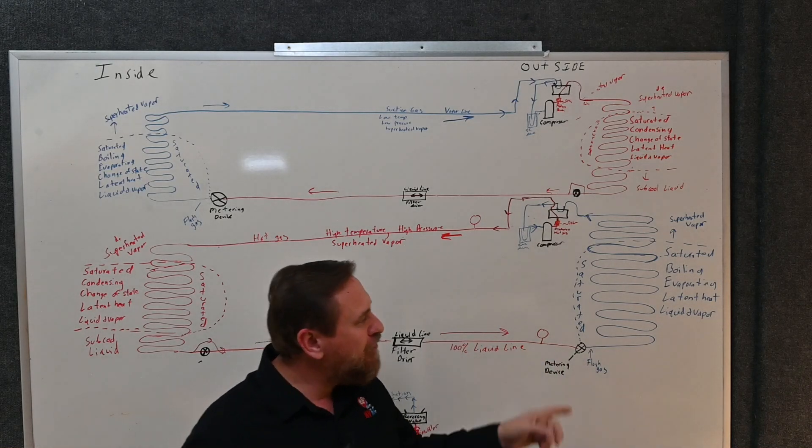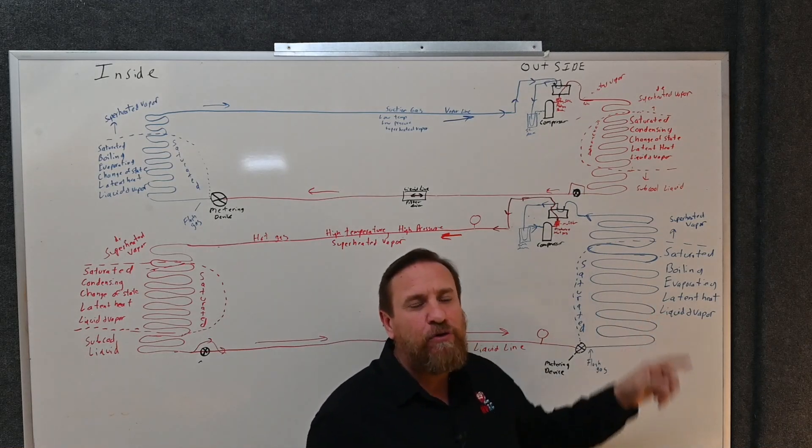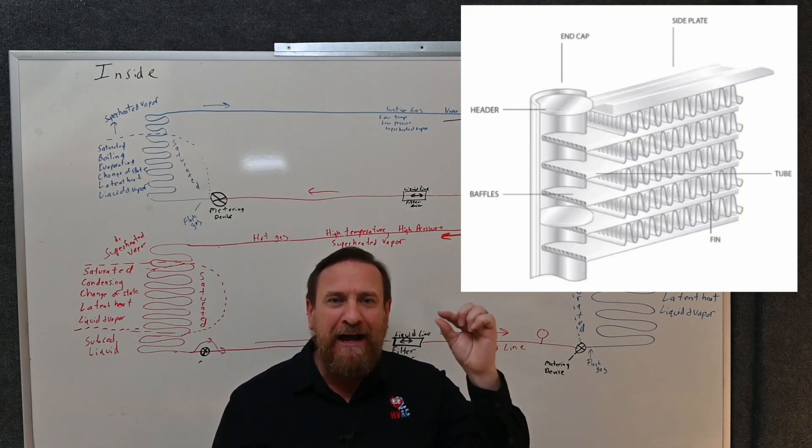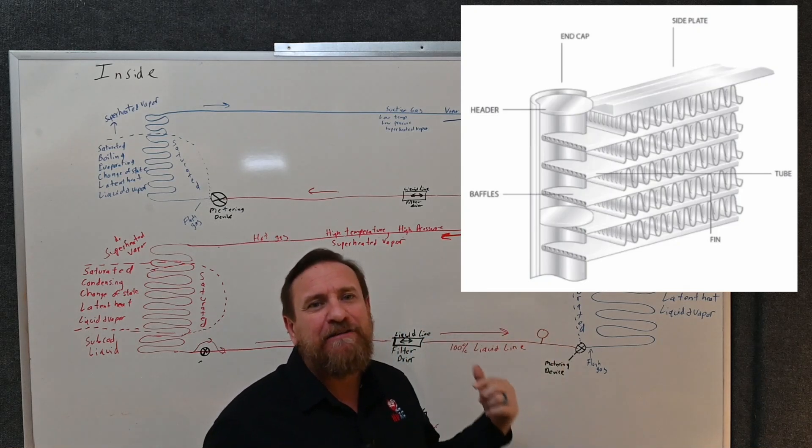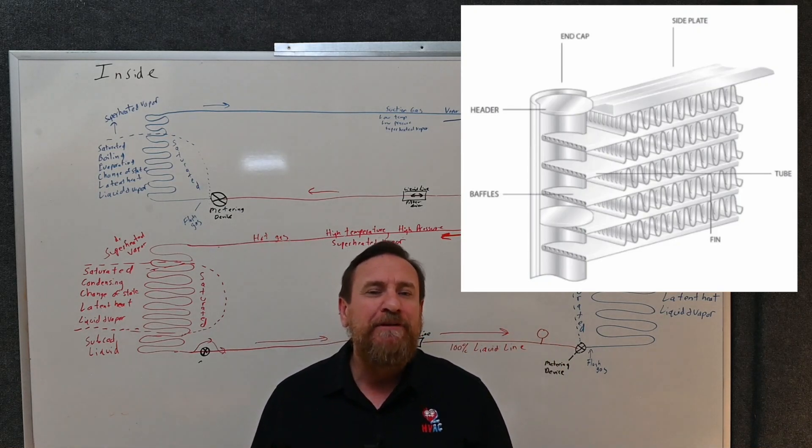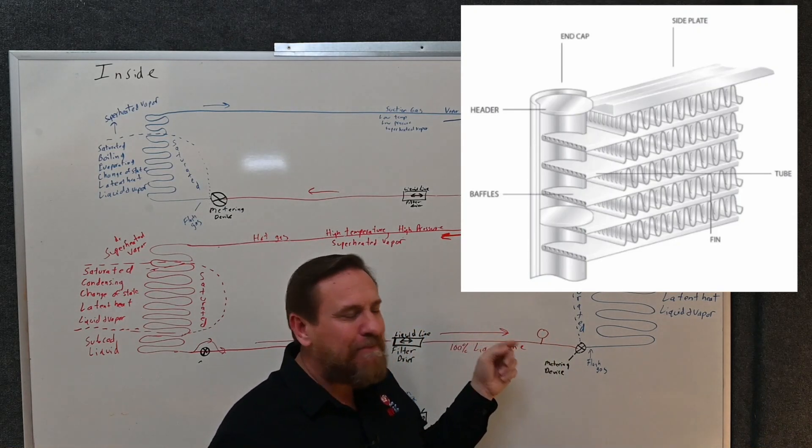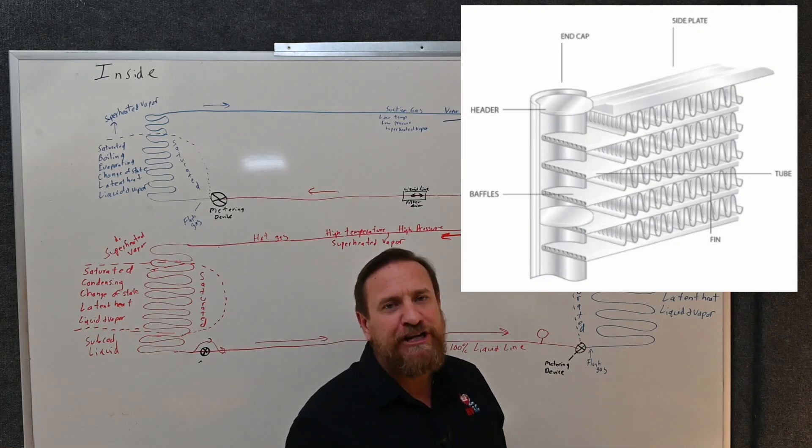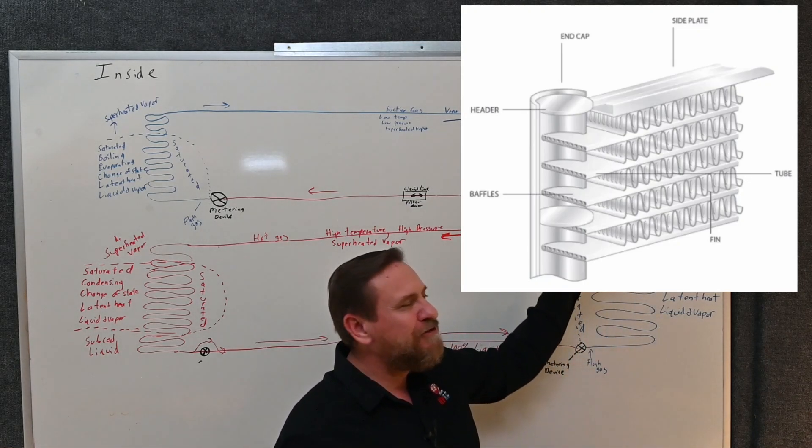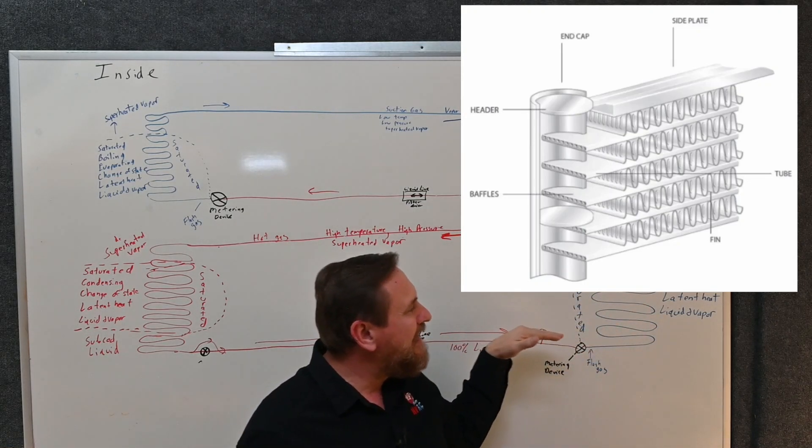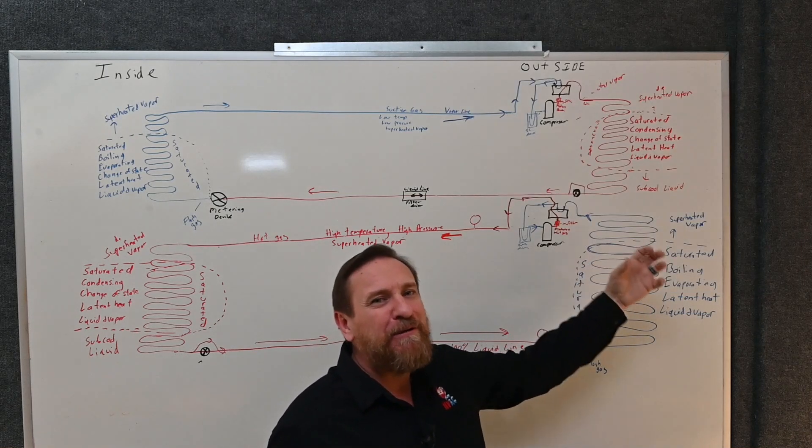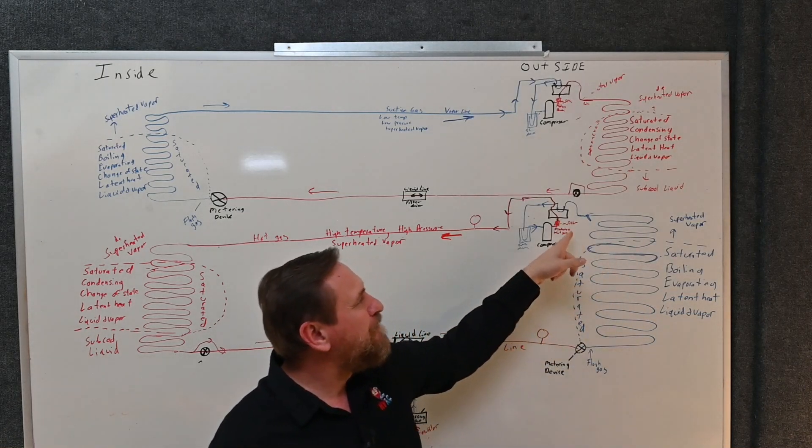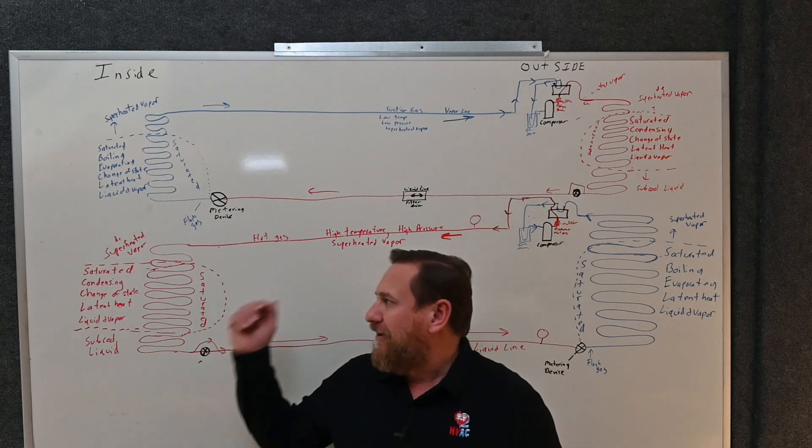It may also be a restriction inside the outdoor coil. A lot of coils now are microchannel, very very small channels. So if somebody's not brazing with the nitrogen flow or not keeping those lines clean, any of that contamination will clog up those little microchannel tubes and it doesn't allow the refrigerant to flow through that outdoor coil. Now we have a restriction. Instead of boiling the refrigerant from a liquid to vapor, absorbing heat, it becomes a restriction. Our suction pressure drops and our head pressure builds.